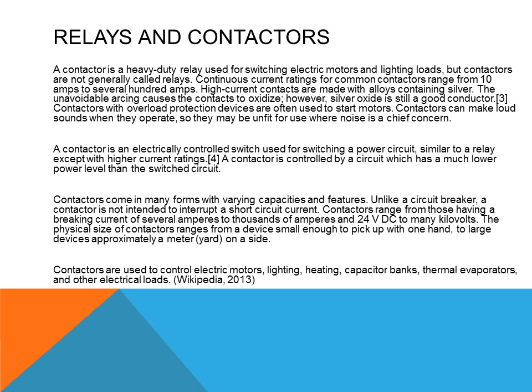A contactor is similar to a relay but is designed to handle higher amounts of current, so it is used on larger types of motors. A relay is designed to handle low current, typically anything less than 20 amps, while contactors handle higher amounts of current, anything over 20 amps.